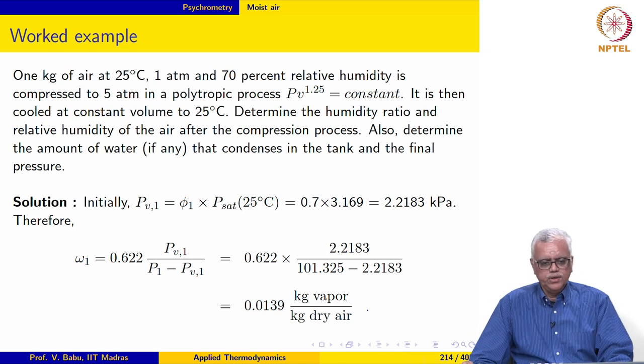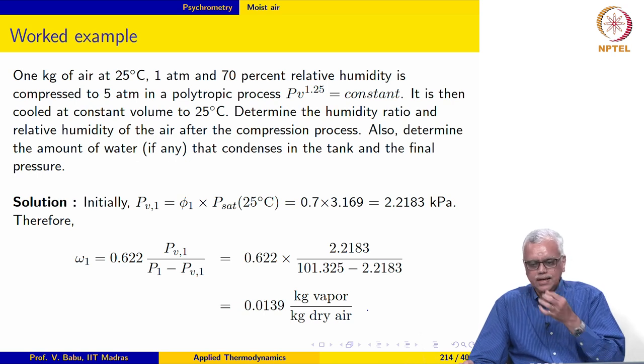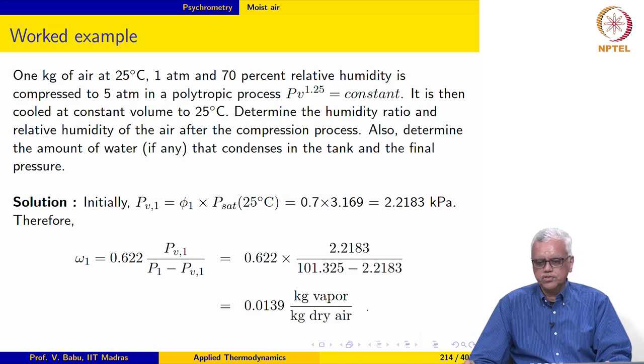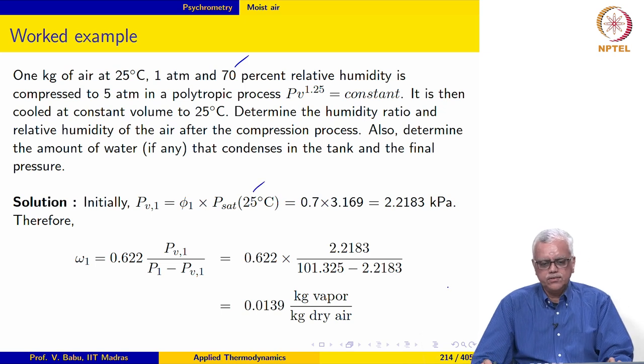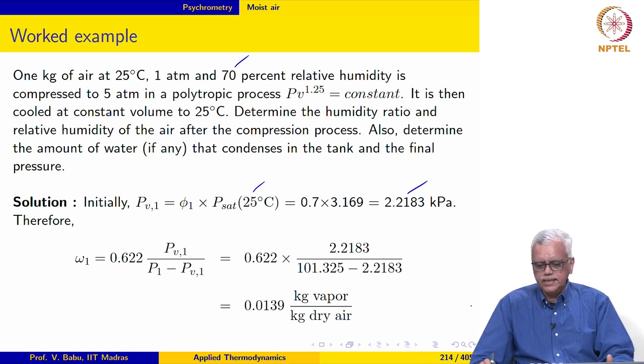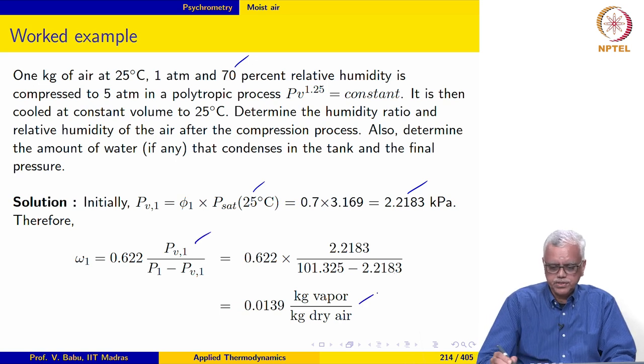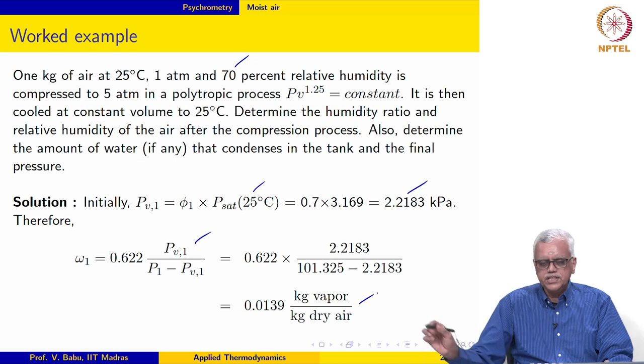The last example: 1 kg of air at 25 degree Celsius, 1 atmosphere, and 70 percent relative humidity is compressed to 5 atmospheres in a polytropic process. It is then cooled at constant volume to 25 degree Celsius. Determine the humidity ratio and relative humidity after compression, and the amount of water that condenses and the final pressure. In the initial state, since relative humidity is given and P_sat of water at 25 degree Celsius is known, the partial pressure of water vapor initially evaluates to 2.2183 kilopascal and the humidity ratio is 0.0139 kg vapor per kg dry air.